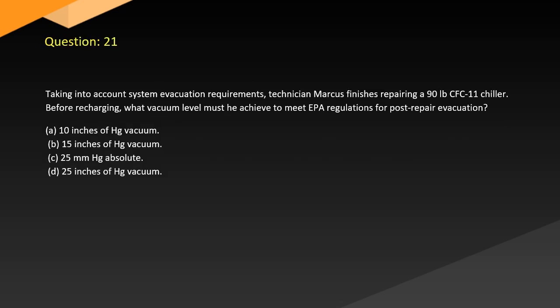Question 21. Taking into account system evacuation requirements, technician Marcus finishes repairing a 90 lb CFC-11 chiller. Before recharging, what vacuum level must he achieve to meet EPA regulations for post-repair evacuation? A. 10 inches of Hg vacuum. B. 15 inches of Hg vacuum. C. 25 mm Hg absolute. D. 25 inches of Hg vacuum.